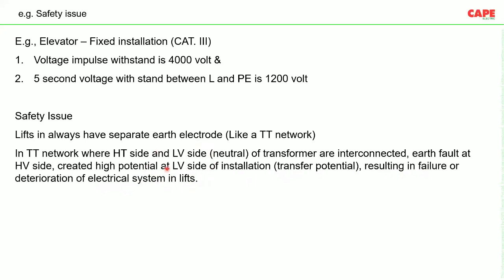So what does this mean? In a TT system, you are getting power supply from a transformer, and at the transformer, if the high voltage side and the neutral of the transformer are interconnected, then in case of any fault on the high voltage side of the transformer, whatever voltage gradient is created on the high voltage side will be transferred to the low voltage side, and will be directly applied on that particular equipment. As a result, the equipment fails. It means a voltage of more than 1200 volt may appear between line and PE. As a result, degradation of the equipment will happen and the equipment may fail.